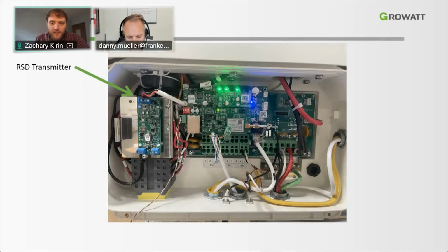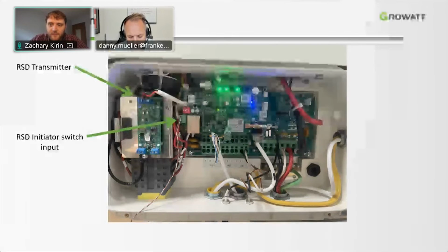Here we can see the components of the MIN system. The rapid shutdown transmitter is built into the inverter. The rapid shutdown initiation switch input is a simple connection wired from the top of the 3-pin connector that you see here. So this would be for a rapid shutdown switch, but you could also use the DC disconnect as a form of rapid shutdown as well. That'll be the initiator. Conversely, the switch is a little bit more necessary for indoor installations, and if it's not readily accessible to the fire department, it's important to have the safety switch.